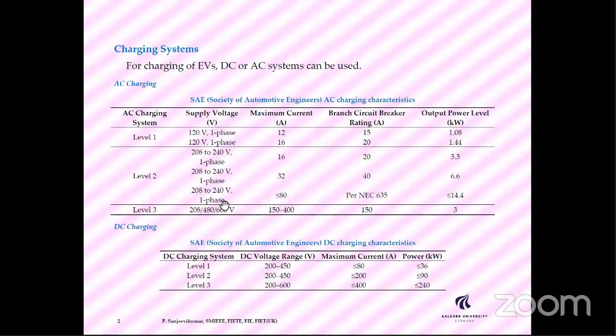For level 3, we can go up to 600 volts high power, and the maximum current is 400 ampere peak, with breaker requirement around 150 amperes, and output power maximum - we can go for a single vehicle 3 kilowatt.